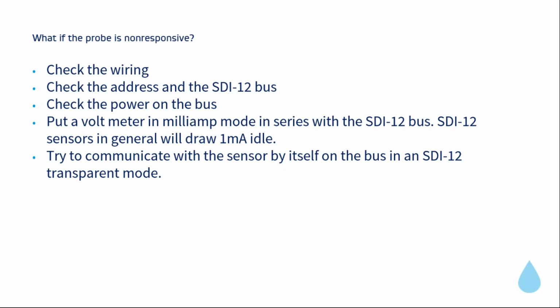You could also take the voltmeter and put it in amp mode, and put the voltmeter leads in series with the ground wire of the bus to see how many milliamps is being drawn from the sensors. Typically, an SDI-12 sensor will draw 1 milliamp idle, so if you have, for example, 12 soil sensors on there, it should be drawing 12 milliamps if idle. During a duty cycle, it'll draw more. The HydraProbe will draw about 10 milliamps during a duty cycle. So you could test that and make sure there's no excessive current being drawn, nothing shorted.